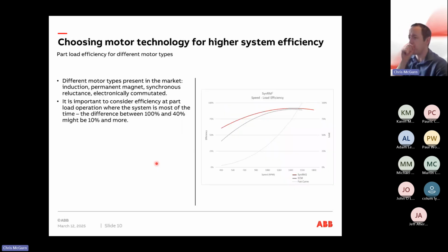Choosing the motor technology for efficiency is important because, like I say, most motors, the nameplate on motors shows an efficiency level which generally meets the regulation, but the regulation is stated at a DOL, a direct online, full speed, 100% load situation. And only in that situation will you meet that required efficiency. So if you're running your motor at slower speeds, the efficiency of the motor itself will actually drop off. So it's important to consider.